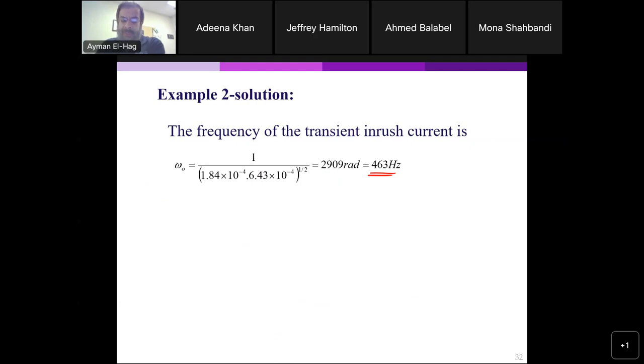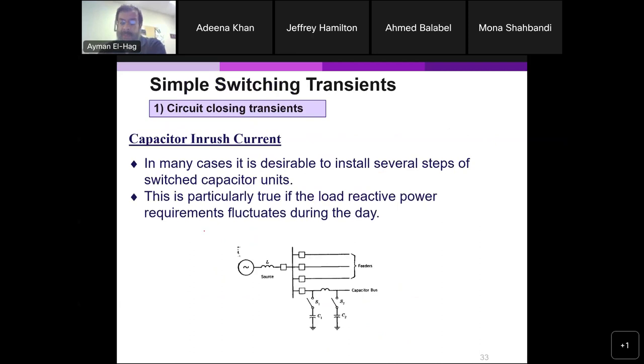So the inrush current, which will lead also to a transient in the voltage, has a higher frequency than your system. Now, this method is used if I connect one capacitor. What if I wanted to connect multiple capacitors? And this is practical. We usually have multiple capacitors in parallel, so we switch them on and off based on our needs, because the consumption of the reactive power is not constant. So we don't just connect one capacitor. Many times we connect one capacitor, and then if the reactive power increases, we connect another capacitor, a third capacitor, and so on and so forth.